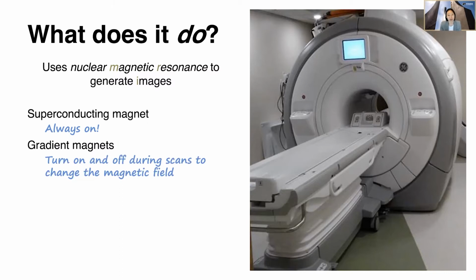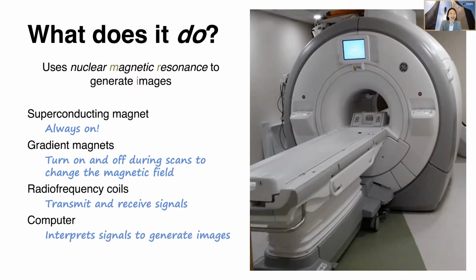There's another set of equipment called the gradient magnets, and turning these gradient magnets on and off helps to change the magnetic field in very small ways. It tweaks the magnetic field inside the scanner so that you can manipulate it. Next, there's a set of equipment called the radio frequency coils, and these are the components that actually transmit and receive radio frequency signals. And we'll talk about that more for sure. And then lastly, of course, everything involves computers, right? So there's a computer that interprets the signal that comes out of the MRI system and uses that to generate images. And all of this is done, obviously, in a patient or a tissue or something like that.